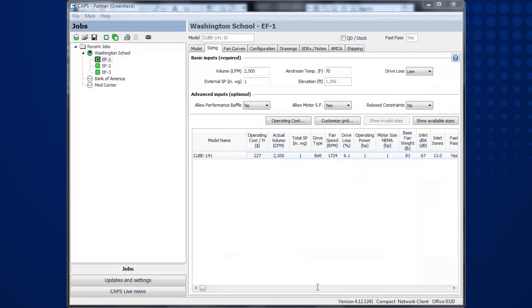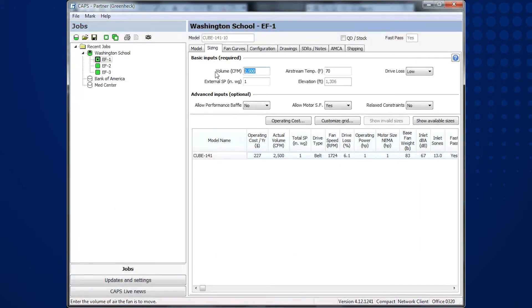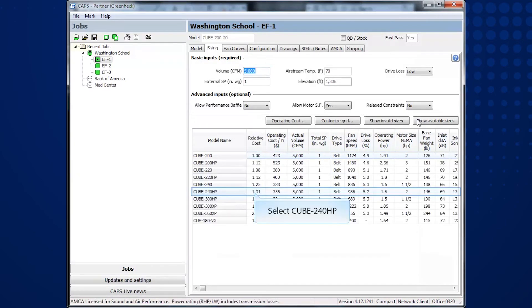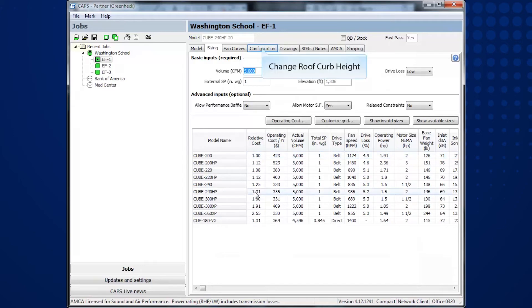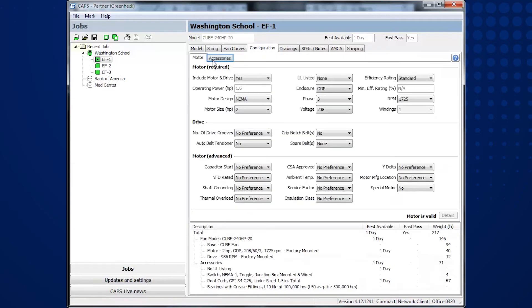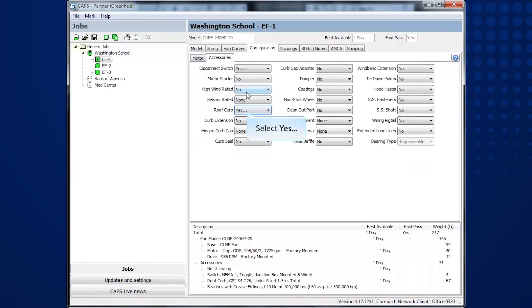Simply go back to CAPS and make your changes. I will change the CFM from 2500 CFM to 5000 CFM. I will then select a different size. In this case, I will select the size 240 HP. And I will change my roof curb height from the default 12 inches up to a size 26 inch tall roof curb.